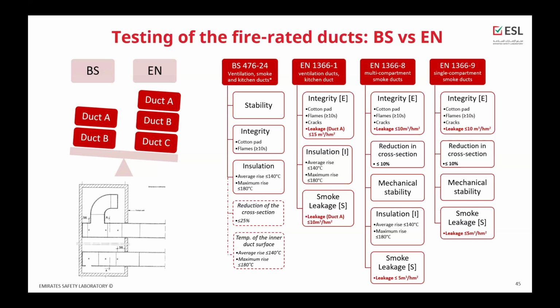There is also no criteria for duct A, where we apply an under pressure of 300 pascals. As a laboratory, we are obligated to report the pressure in duct A as a graph. However, if this duct A starts losing its air tightness and the under pressure starts dropping, there is no criteria to say the duct has failed. Whereas EN clearly mentions criteria for leakage, either as an additional classification mark S for smoke leakage, or in the integrity criteria as one of the criteria for the integrity of the ventilation duct, kitchen duct, and the smoke ducts.